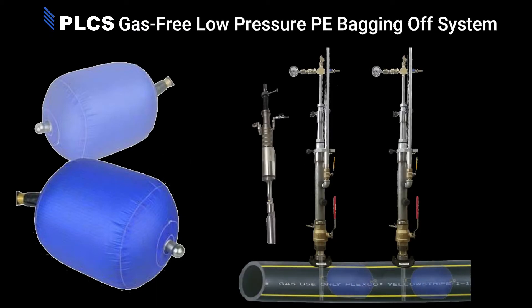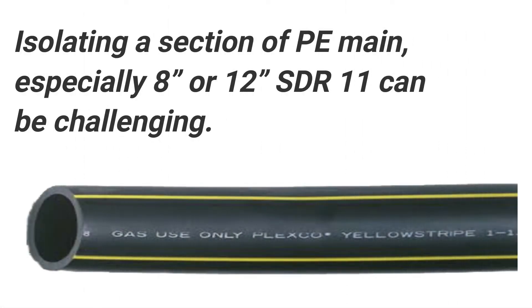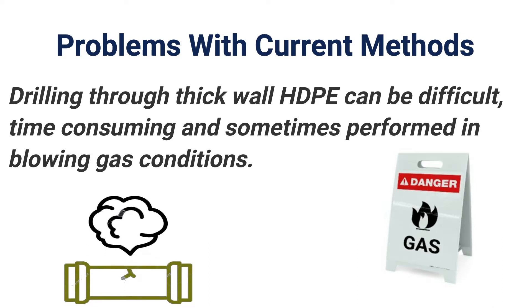The PLCS Gas-Free Low-Pressure PE Bagging Off System. Isolating a section of PE main, especially 8-inch or 12-inch SDR-11, can be challenging. Drilling through thick-wall HDPE can be difficult, time-consuming, and sometimes performed in blowing gas conditions. Using off-the-shelf hole saws to access the main can create shavings that fall into the pipe, causing blockages at other locations within the gas system.